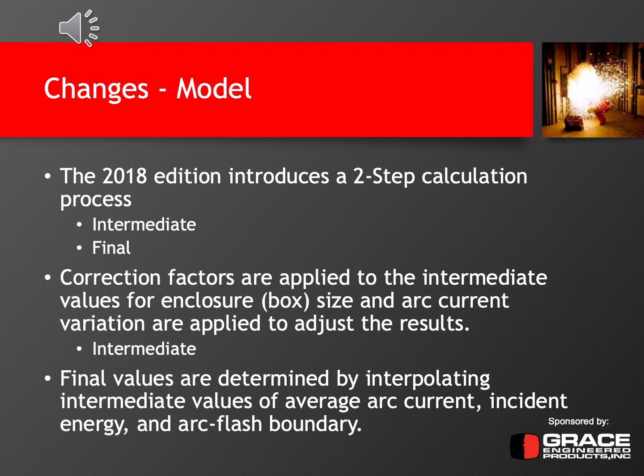Each of the intermediate calculations requires a three-equation calculation that takes into account the electrode configuration and some of the coefficients found in tables for certain voltage levels. And then the final calculation also takes into account other correction factors applied to the intermediate values, like enclosure box size and arc current variation. Basically, you calculate the arcing current at the 3 fixed voltages, and then you use a correction equation and correction factor to interpolate to your actual system voltage. So say you calculate it at 600 volts, you would take that 600 volt result and interpolate it down to your 480 volt system. And this is done at intermediate values of average arc current, the incident energy, and the arc flash boundary.